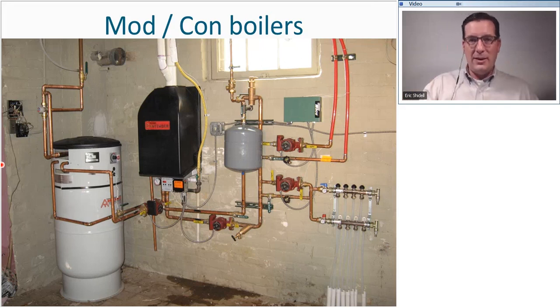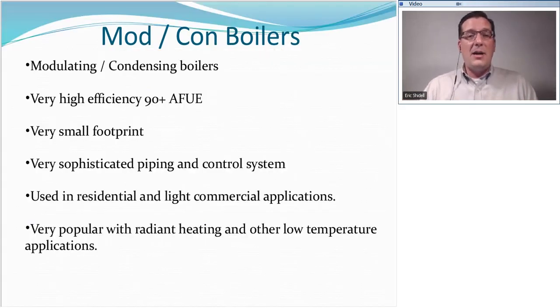At the end of our course in Section 6, we're going to deal with these systems a little bit more heavily. So modulating condensing is what they stand for. Very high energy efficiency, 90-plus AFUE. This does mean they are condensing, which means that they are going to drain water out as a normal part of their operation. It also means that they're going to be working their best in low water temperature applications, generally under 140, under 130 degrees, to maximize that condensing potential.